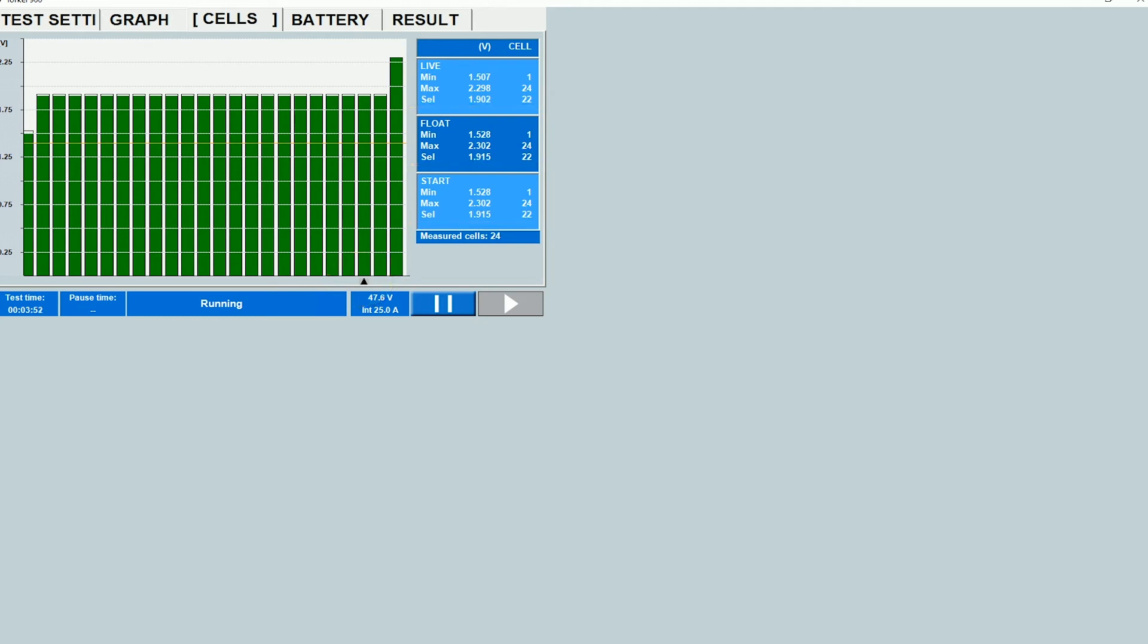The standards allow you to pause the test once during the entire duration of the test. The reason to do that would be to bypass bad cells. When you're doing this discharge test, different cells discharge at different rates based on their condition. The bad cells would discharge faster, their voltages would drop sooner. If you see them approaching polarity reversal, then what you can do is, and the warning limit helps you out with that. When the cell voltage is dropped too low, the instrument gives you a warning.